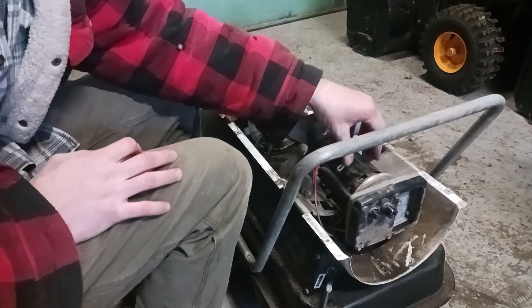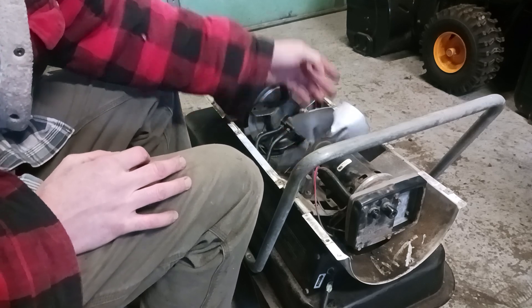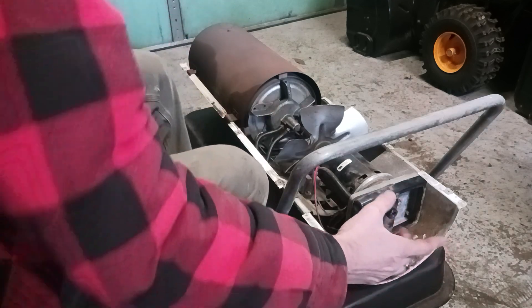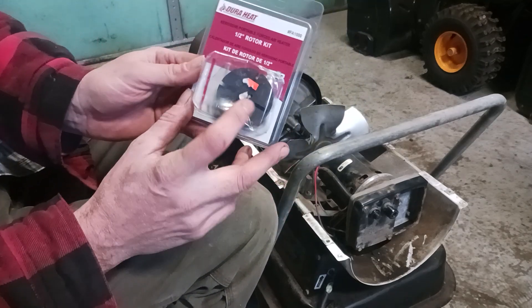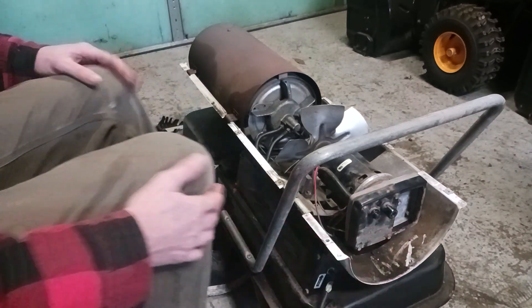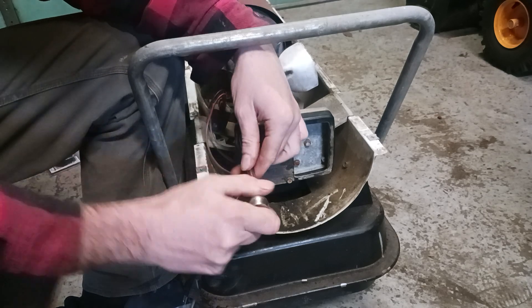What I'm talking about here is the motor, which was not turning. I turned it and heard something break. When I plug it in, everything kicks on but it doesn't get fuel. Back here there's a forced-air heater rotor kit that most likely is broken. I'm going to show you how to get to that. There are four bolts here — five-sixteenths.